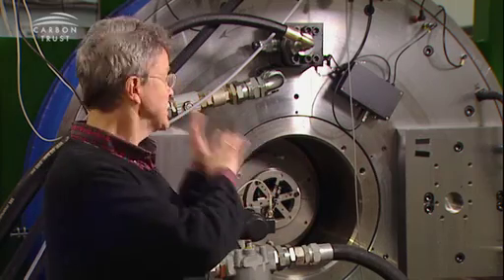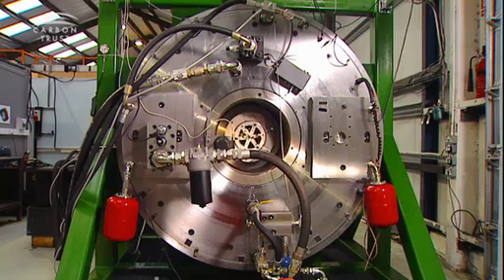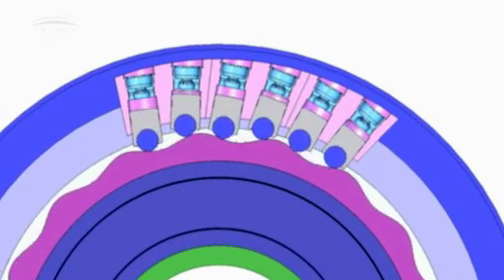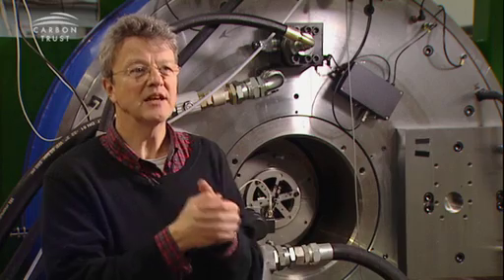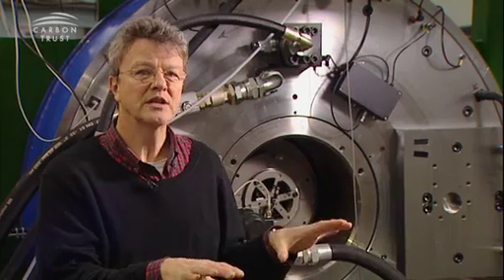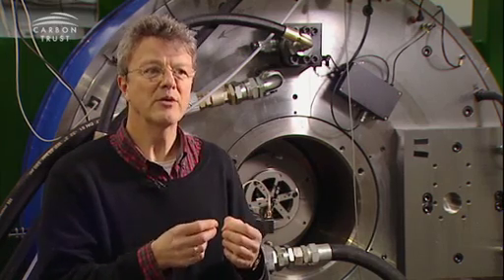What you have to imagine is that inside this machine there are many cylinders with pistons moving in them. As the shaft goes around — we call it a ring cam because there's actually a cam inside — each time the shaft goes around, each of those 68 cylinders does a pumping stroke. With digital displacement, we can decide just when the pumping stroke is about to start, whether we actually want this cylinder to pump or not. Maybe we're working at part load at 10% of the full rating — if that's the case, the computer will automatically disable that cylinder by controlling the valve at just the right moment.